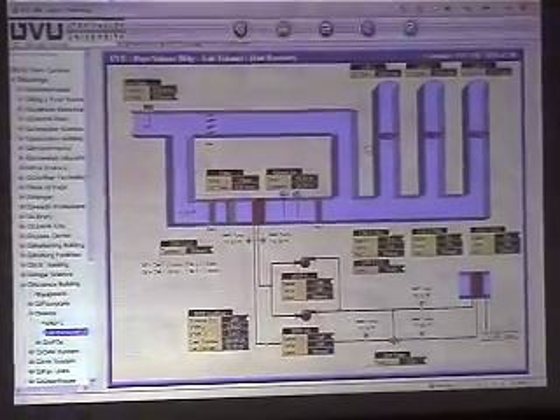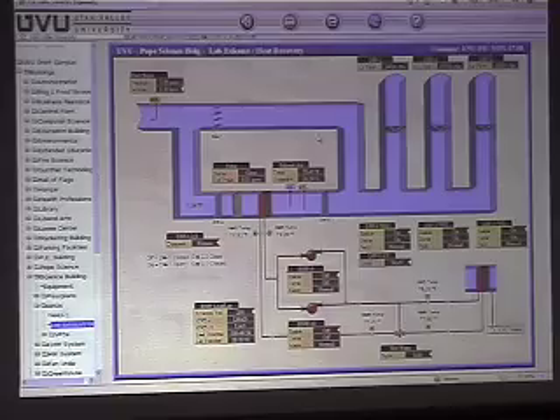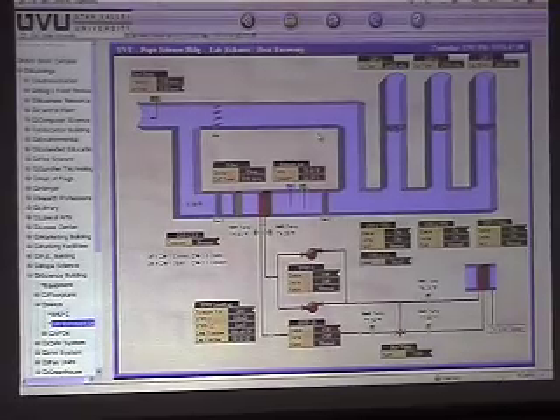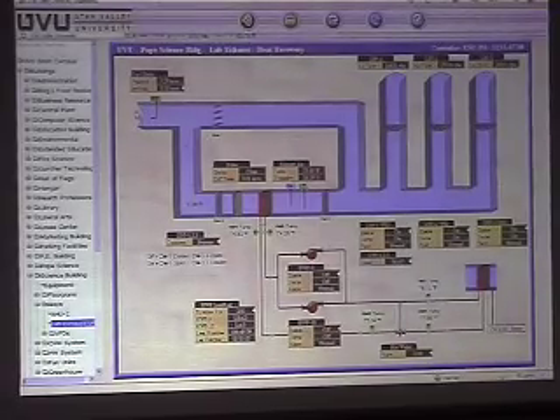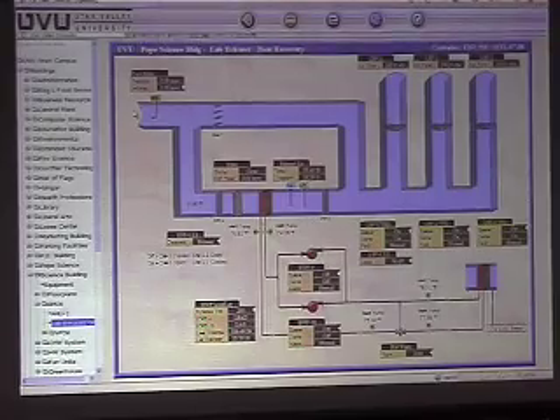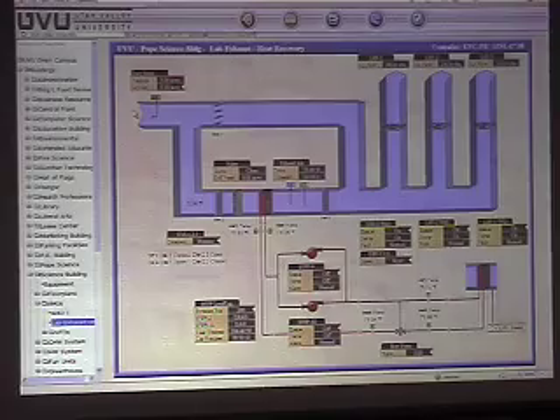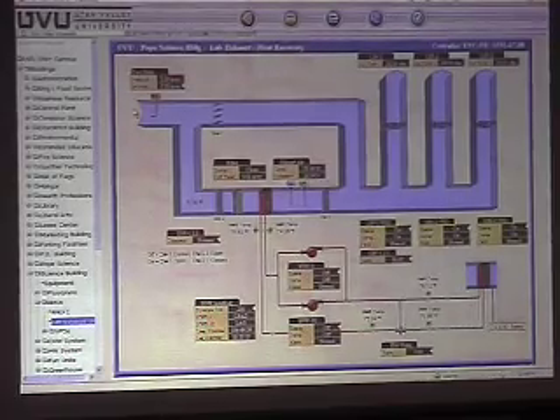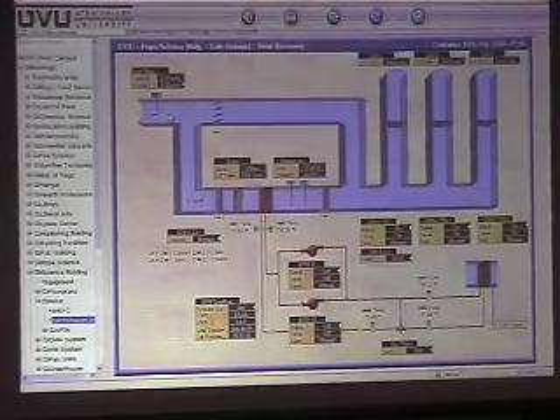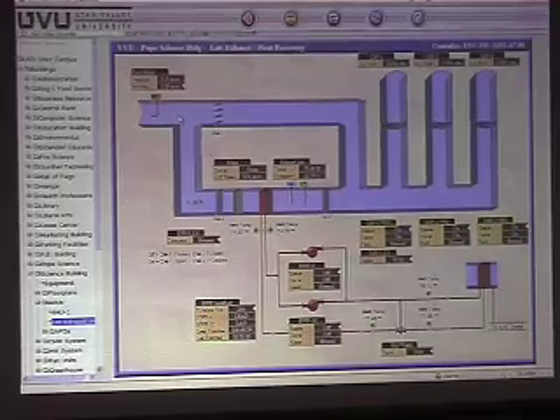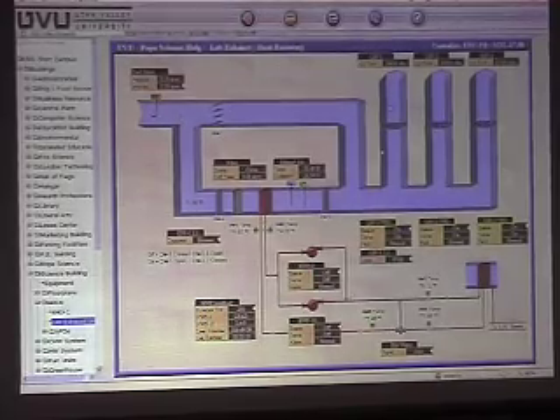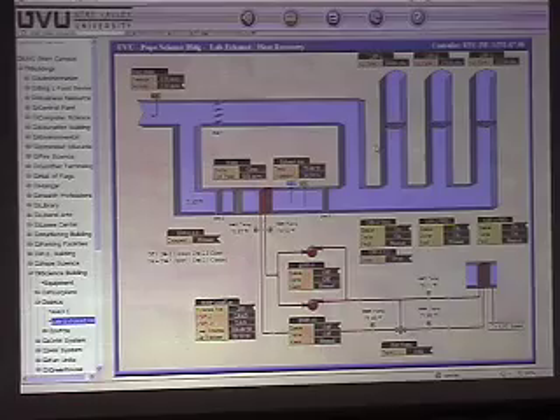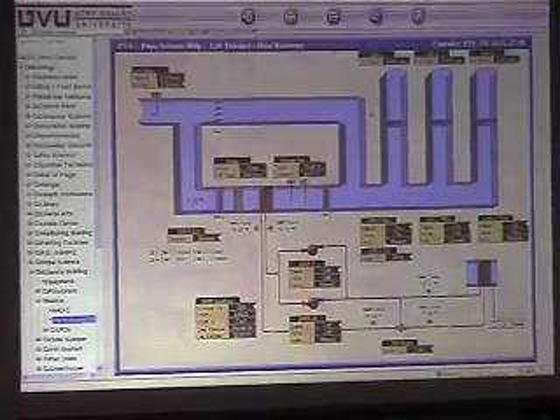Well, that brings us to this screen, which is for the lab exhaust fans. So you've got dedicated exhaust duct from each of the science rooms that are tied into the entire system, and they all come back up through a dedicated duct that feeds to these three exhaust fans. So they're isolated from the return air of the air handler, so it doesn't mix at any point.